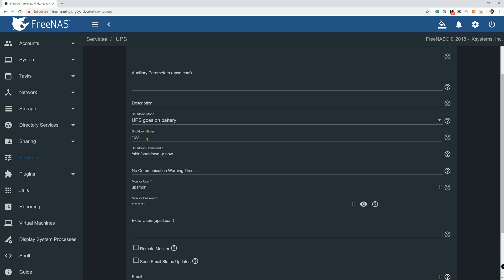Shutdown timer. So right now I set it at 120. So this value right here is in seconds. So I set it at 120 seconds or 2 minutes. So what it does, it's going to start countdown the minute that it lost the USB connection or serial connection to your UPS. It's going to start countdown. If the power's back on, the system is going to back to normal. It's not going to initiate a shutdown. But after 120 seconds countdown and it's still lost connection with the UPS, it didn't get a USB connection or serial port connection, then it's going to initiate a shutdown.